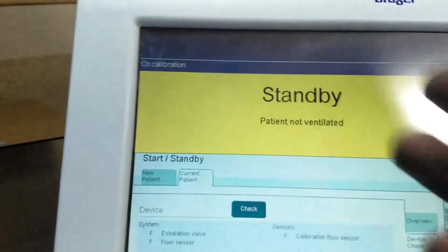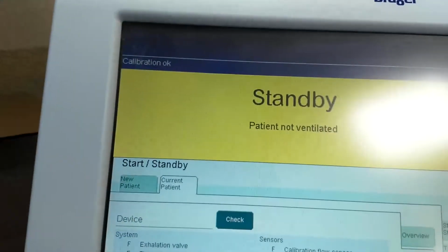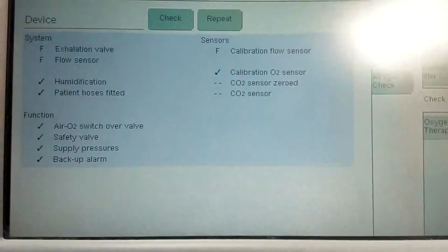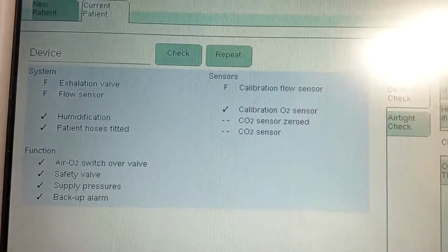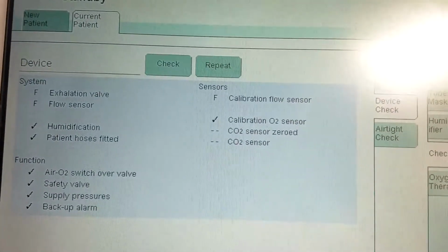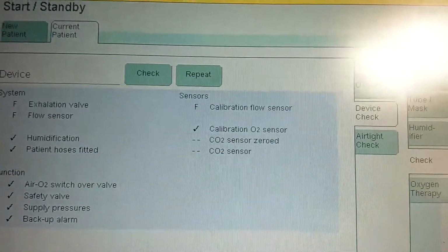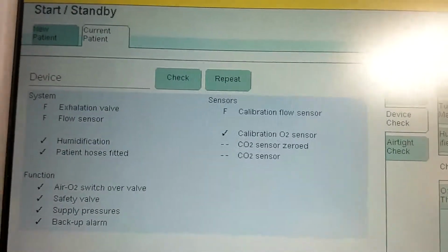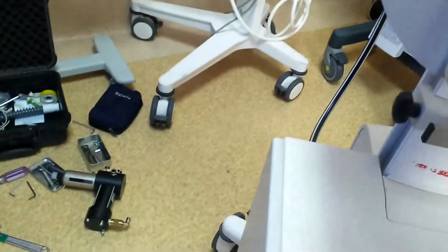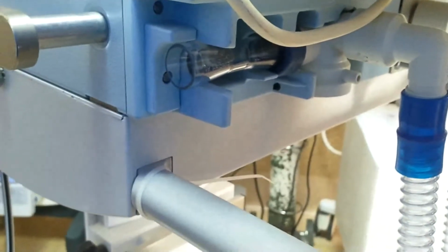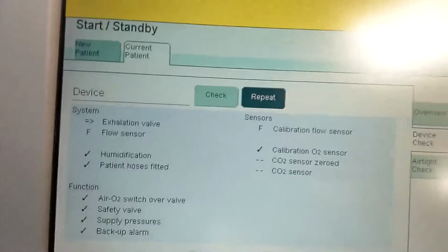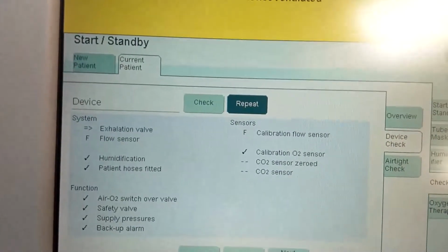So it is doing O2 calibration. O2 calibration passed. Okay, so here when you see the test, the expiratory valve flow sensor test failed, flow sensor calibration failed. So three tests have failed, remaining tests have passed. So I will connect this. Okay, I have connected the new flow sensor here. Now we will repeat the tests which failed. Only the tests that failed are being repeated.